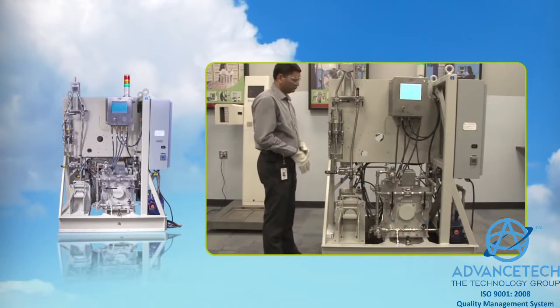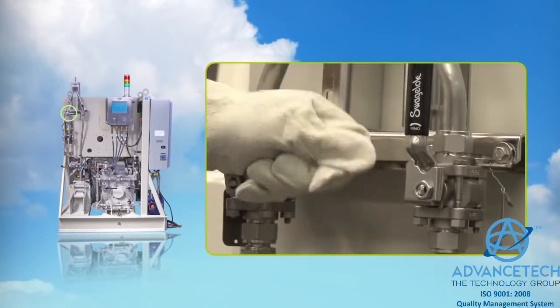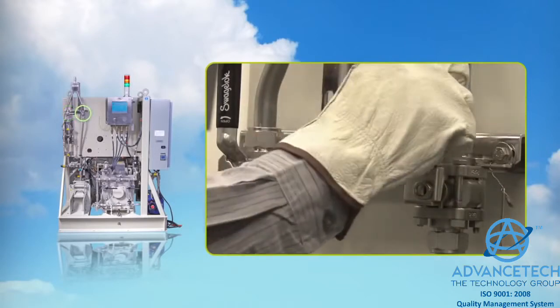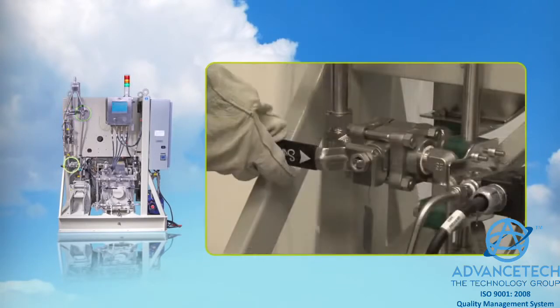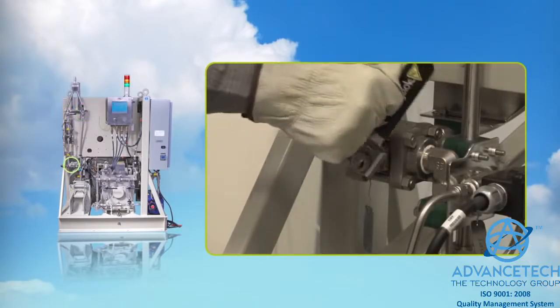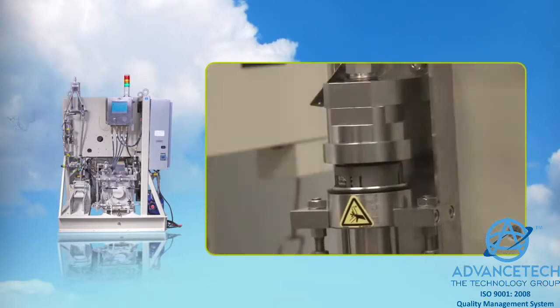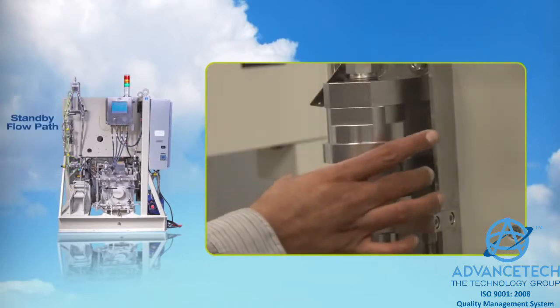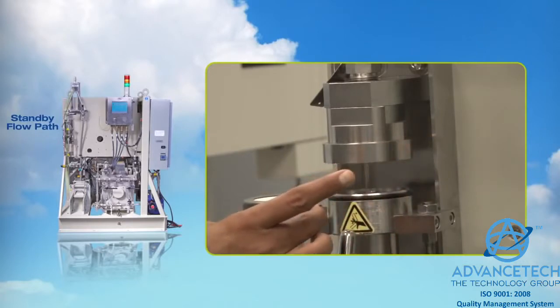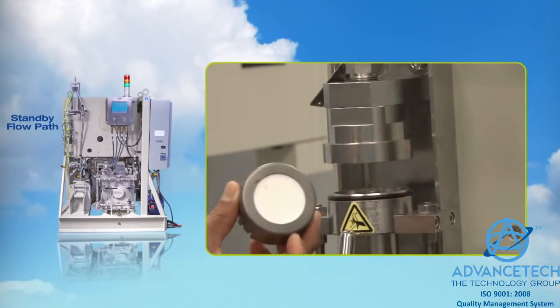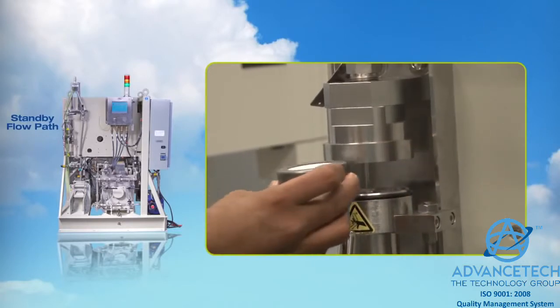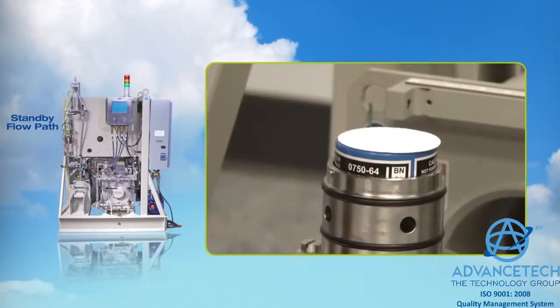When a filter change is required, the operator can bypass the normal flow path and direct the sample through the standby flow path by simply changing the position of the valves. The standby flow path also routes the sample through a filter paper and charcoal cartridge in the FA200 filter assembly holder, so that collection of particulate and iodine samples continues during the filter change.